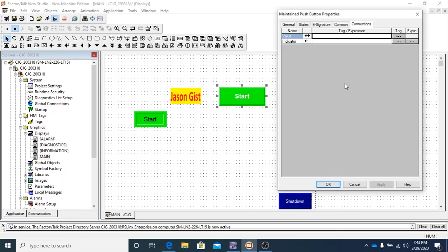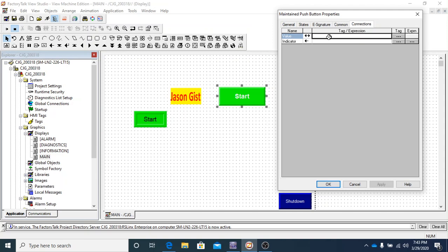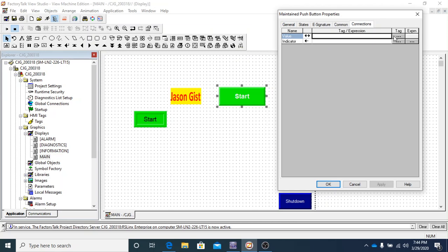The connections tab we can't do much with in the video, but we'll do more in the lab setting. But this is where you're going to tie it to something in your program with your processor so that you can actually tell the HMI to tell a certain tag in the processor to function. So instead of using a hard input on a push button on the outside of our panel, we're going to use one off the HMI. This is how it talks to that spot or that instruction in your program. This is how it knows where to go to.